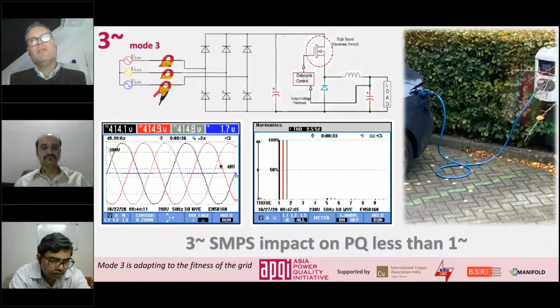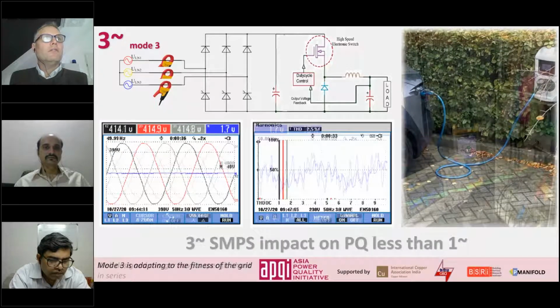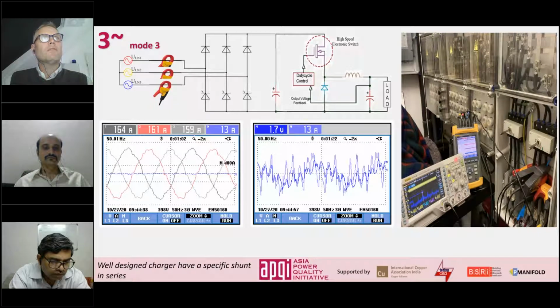So what you're giving the inverter, that's what it will be using. When your voltage THD is very, very bad, it will also draw and put out very bad current. So let's take a look at the three-phase switch mode power supplies. The voltage is good. Now I'm looking at the current, 160 amps flowing through every phase, and here you see the neutral wire is 13 amps.